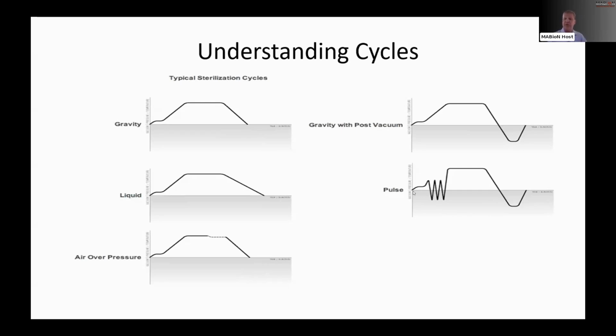But let me explain what happens here. You have the purge come in, and you see how sharp these lines are, and they go from pressure down to vacuum, pressure, vacuum. And what that's doing is when you have a pre-vac cycle, you pre-warm everything up. Now what happens is you're going to put the pressure in. It's going to squeeze it. The steam's going to drive in. It starts penetrating. It turns to liquid. So now you're blocking the steam from actually penetrating what you're trying to get it into.